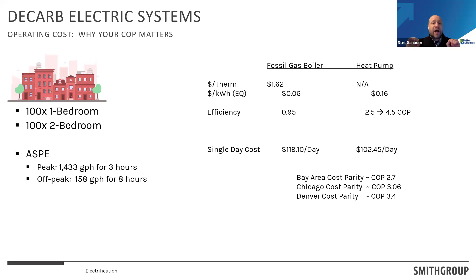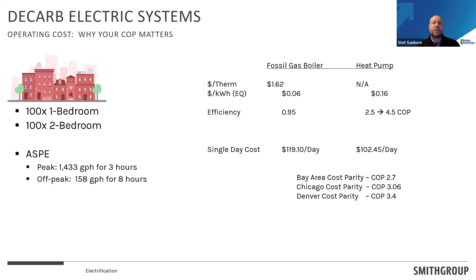So if I look at the cost for a certain region, I want to target a heat pump selection, a coefficient of performance, that I know will produce lower cost hot water utility. It's different in every region. For the Bay Area where I live, I need a COP of 2.7. In Chicago, you might have to hit 3 or above. Remember that in cold climates that definitely means looking at wastewater heat recovery. In Denver, because of the balance of utilities there, you need a really large COP to reach cost parity. So we always want to focus on cost parity as well as efficiency, and find other efficiency measures that support that work.